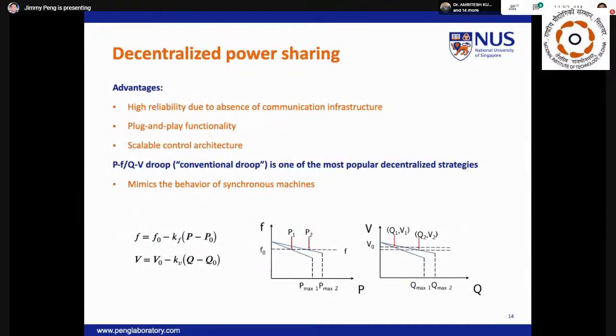So to summarize, the key advantages of decentralized power sharing are improved reliability, in the context that the inverter-based generators do not need to depend on a communication network. The plug-and-play nature of this decentralized control enables equipment to be installed or removed without imposing major changes to the existing operating framework. And these lead to the third benefit of being scalable to accommodate many equipments over a period of time. Regarding proportional power sharing, Droop in terms of PF and QV can be deployed.